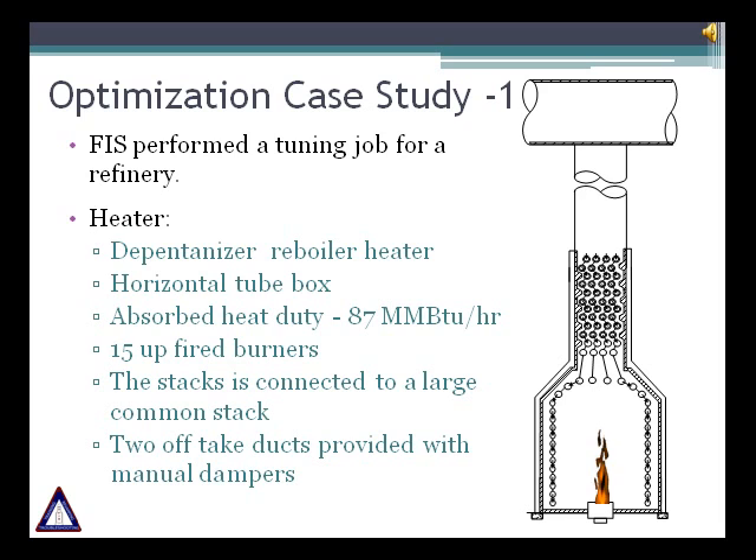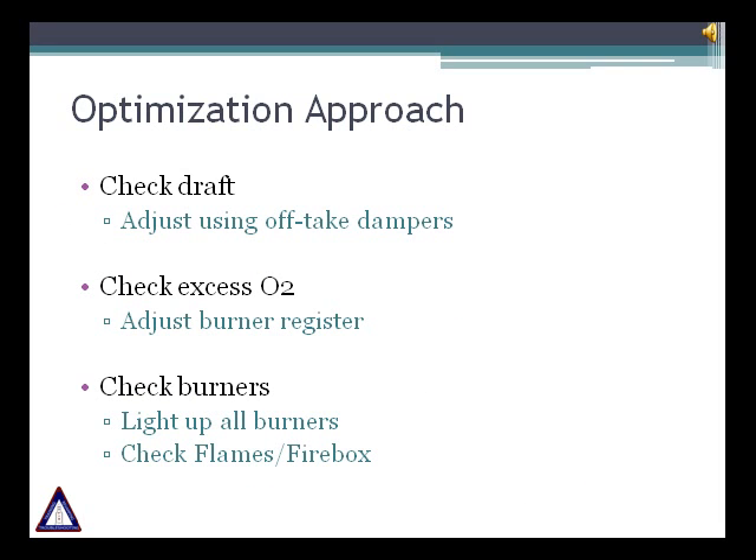A few months ago, our company had the opportunity to perform a tuning job for a refinery. The heater was a depentanizer reboiler with horizontal tube box and 15 up-fired burners. The heater has two off-take ducts provided with manual dampers, both connected to a large common stack. The absorbed heat duty of this fired heater is about 87 mm BTU per hour. To optimize the heater, our team checked three points: the draft, the excess air, and the burners. For the draft they made adjustments using the off-take dampers. The FIS team adjusted the burner registers to get minimum excess air, lit up all the burners, and checked the flame in the firebox to diagnose any problems in the radiant section. The results are shown in the following graphs.